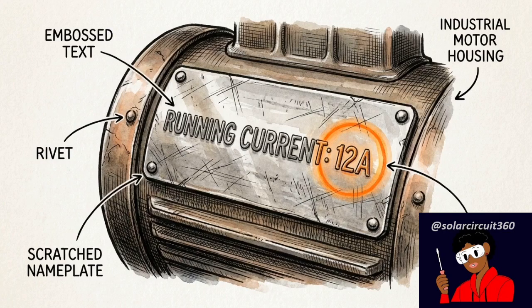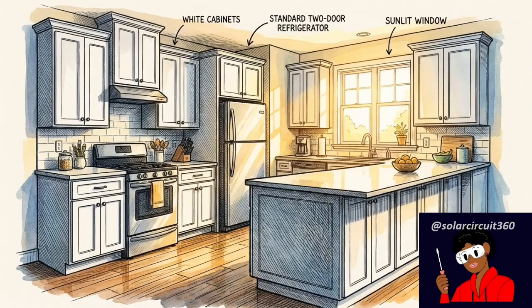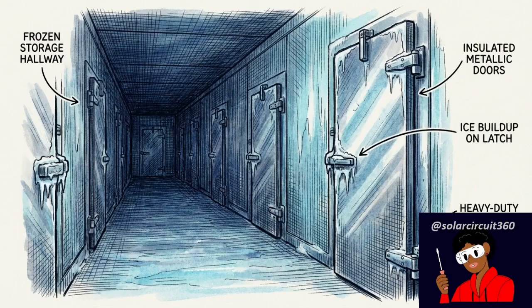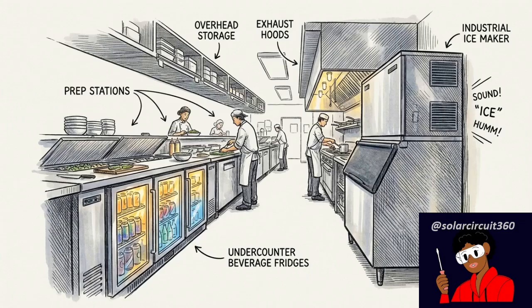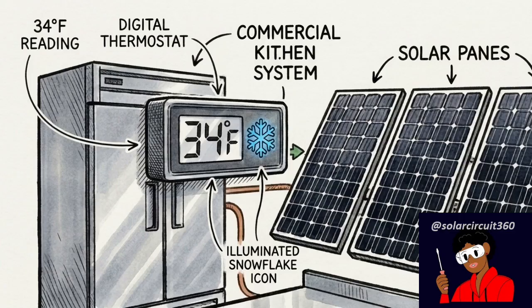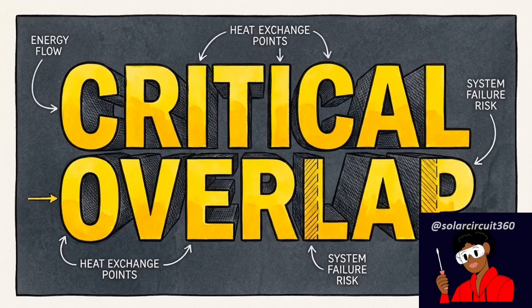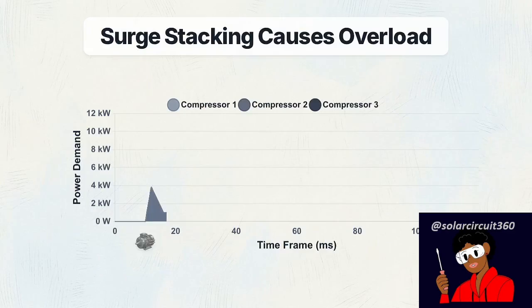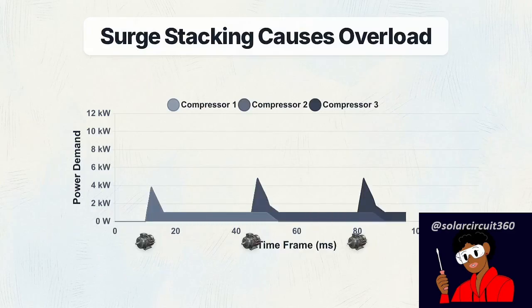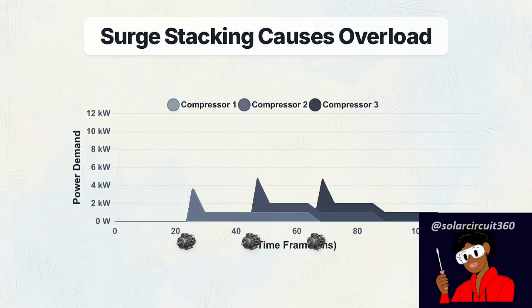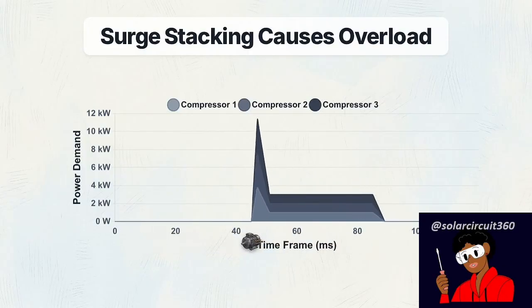A typical residential kitchen has one refrigerator. A commercial kitchen often runs deep freezers, walk-in coolers, beverage fridges, and ice makers all at the same time. Because these units cycle on and off autonomously to maintain internal temperatures, you eventually hit a statistical inevitability called surge stacking. Multiple compressors will try to start at the exact same millisecond. When 3 of these individual compressor curves happen to overlap, their initial startup spikes stack on top of each other. The combined demand violently pierces right through the 10 kilowatt limit of the inverter.